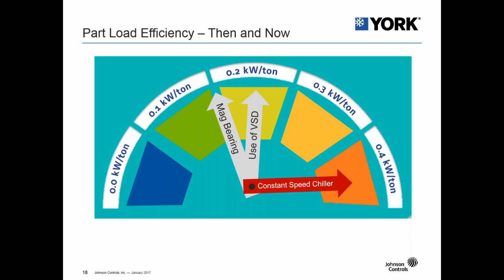Then as magnetic bearing technology started to come into the marketplace, that started to push the part loads using both the mag bearing and the variable speed technology. We were almost, as an industry, getting below 0.2 kW per ton at part loads, breaking into the 0.1s. But now with the York YMC squared, we're able to get down below 0.1 kW per ton with very low entering condenser water temperature at part load points.